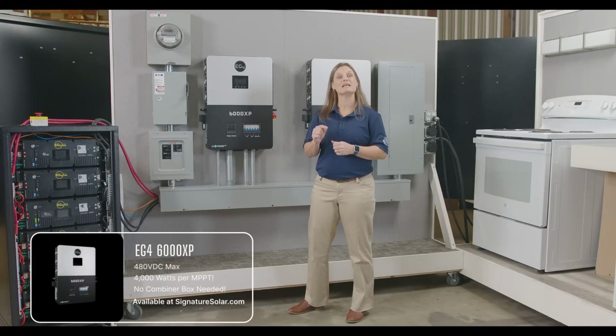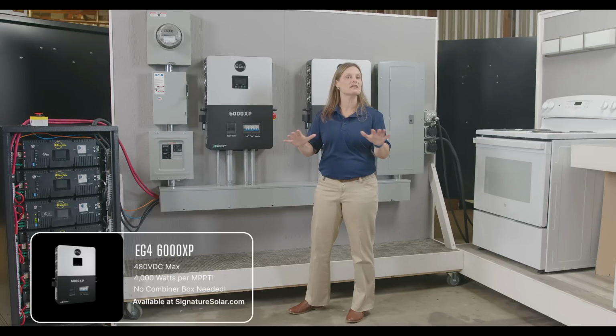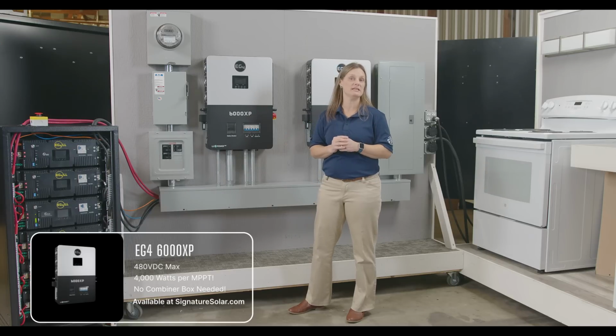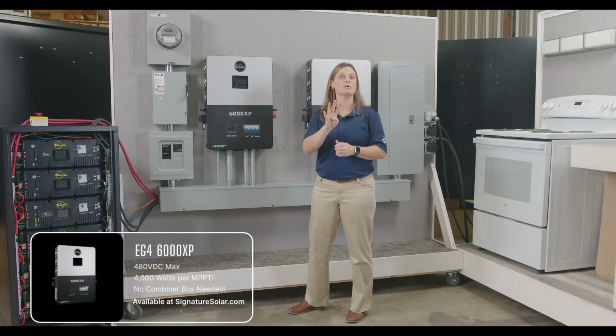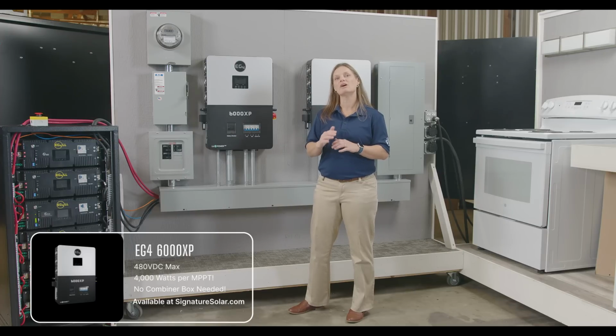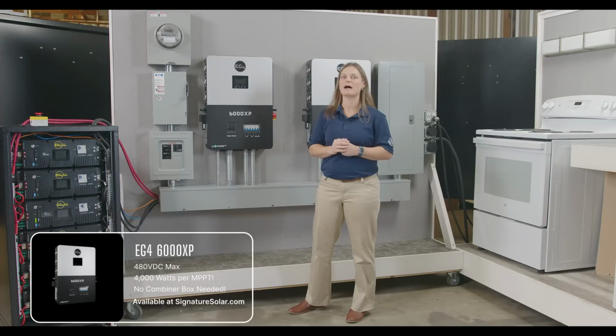This inverter has a maximum recommended PV input of 10,000 watts, intelligently spread across the two MPPTs, each utilizing up to 4,000 watts. What really makes this meaningful is that the high wattage allows for high voltage input, 480 volt DC across the two MPPTs. Not only does this optimize energy capture, but it also streamlines your setup by completely eliminating the need for a combiner box. It's efficiency and simplicity all wrapped into one powerful feature.